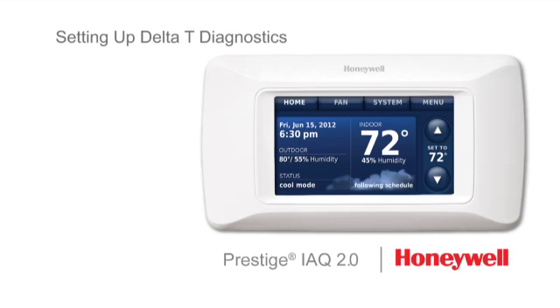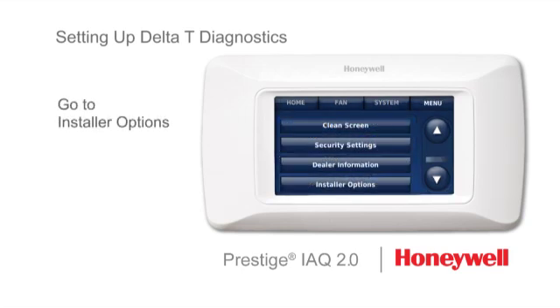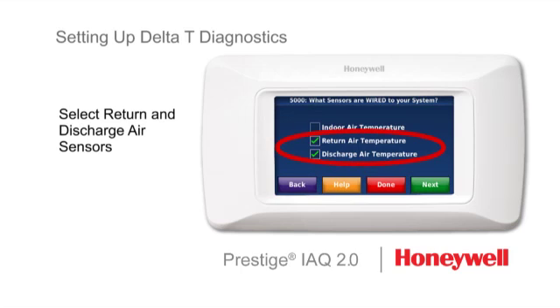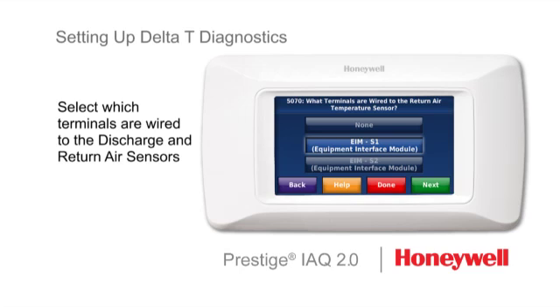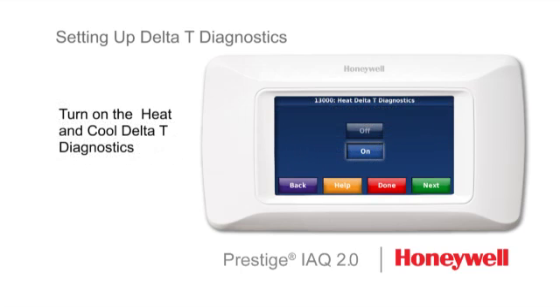To begin the Delta T setup process, go to the installer setup screens on Prestige. The first step is to select the return and discharge air sensors. Step two is to select which terminals are wired to the discharge and return air sensors. The sensors are connected to the S1 and S2 terminals at the equipment interface module. Finally, you'll be prompted by the setup screens to turn on the heat and cool Delta T diagnostics.